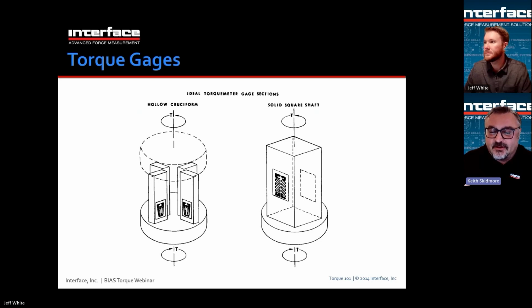Some torque sensors get a little more complicated in that they have features on the shaft, such as machining it down into a cruciform, such as shown on the left, or even more complex shapes, I-beam type shapes, T cross sections. But basically, they all do the same thing. As you apply a torsion, the strain gauges or the strained area is where the measurement is made.